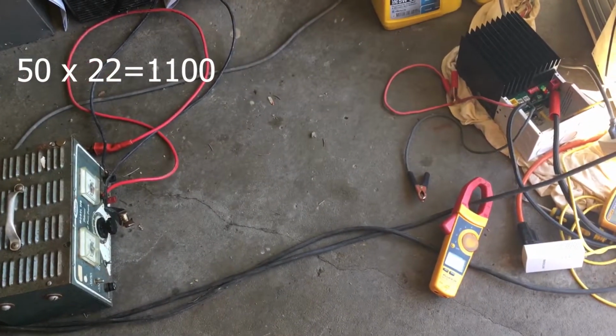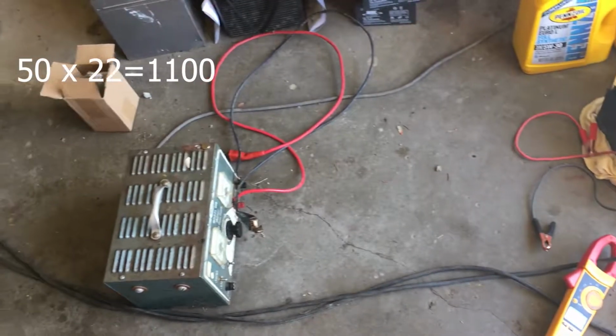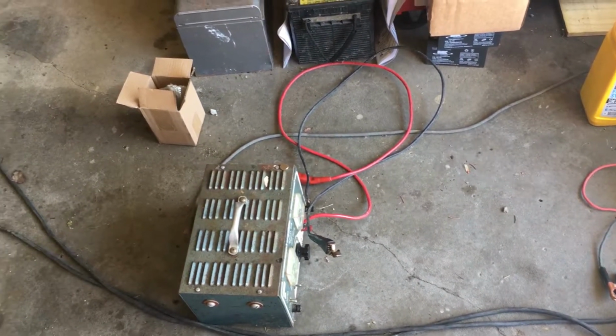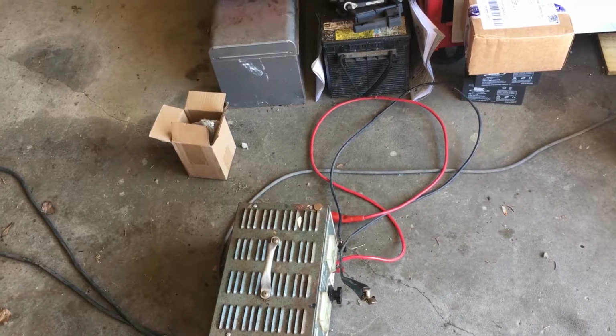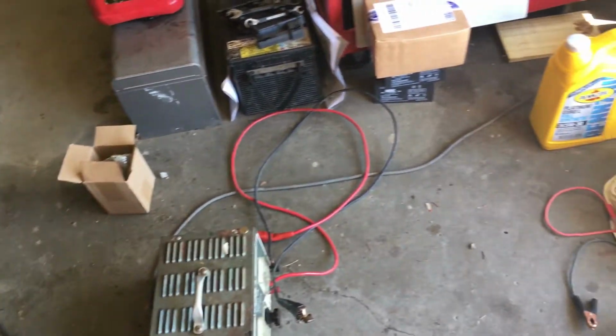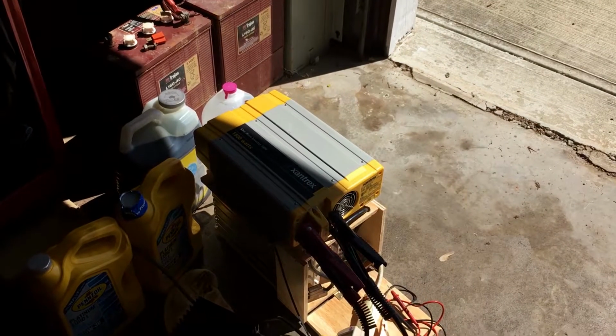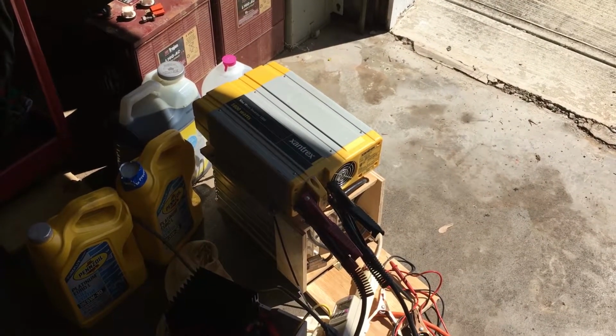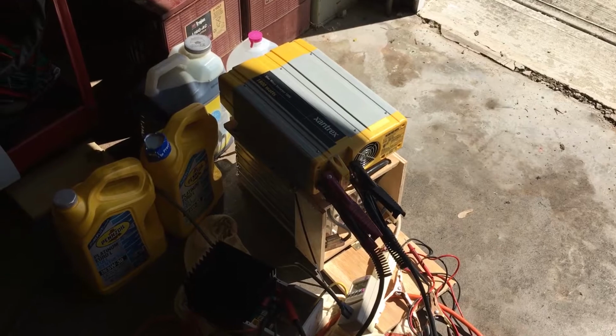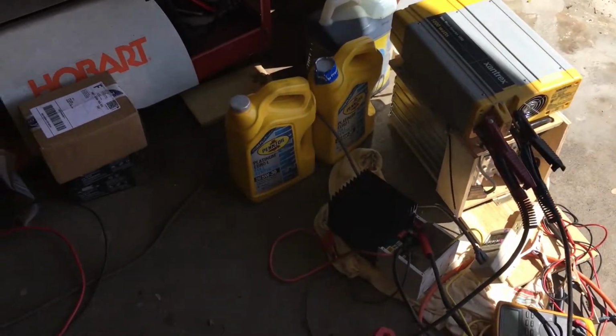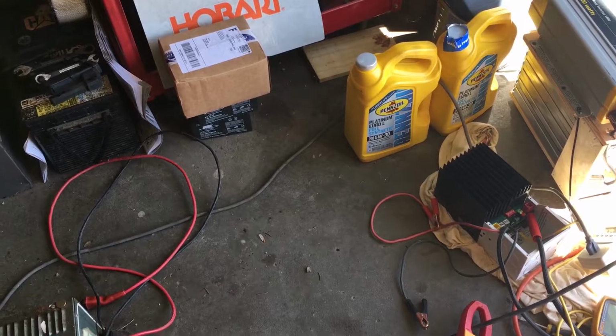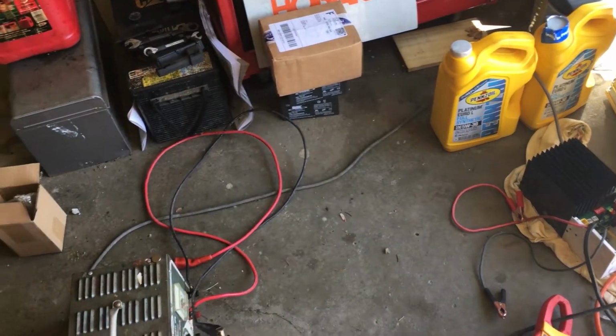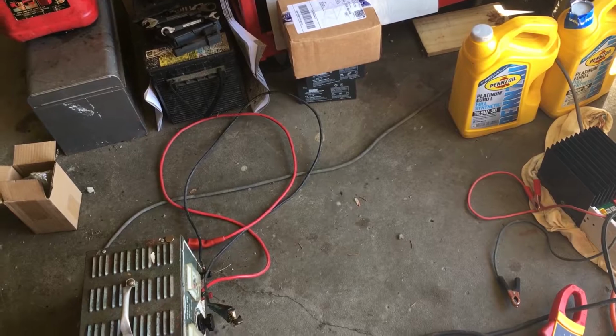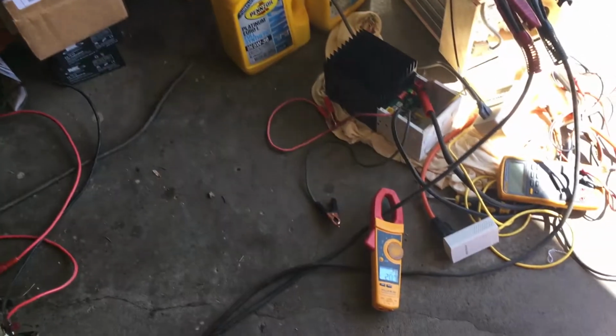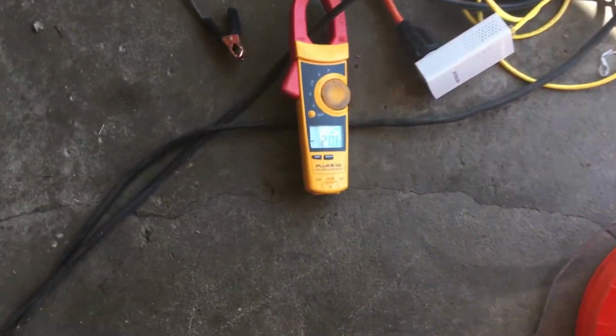The issue with pulling 50 amps is that you have to be careful how fast you charge the battery, because the faster you charge it, the hotter everything gets. I believe the 1C rate on these batteries, since this is technically a 66 amp hour battery, would have been okay at 50 amps. I don't think it would get too hot, but 20 amps is a much safer rate.